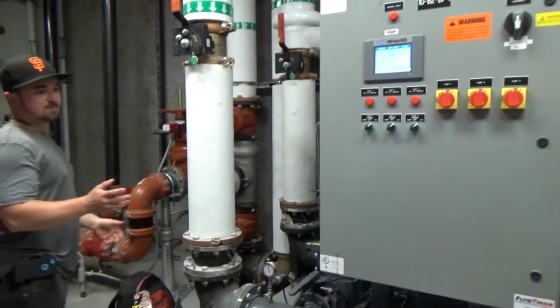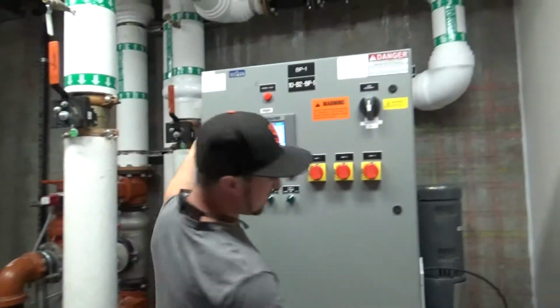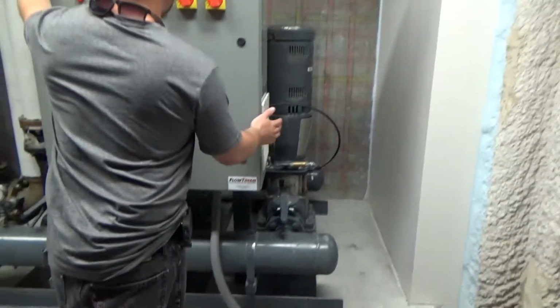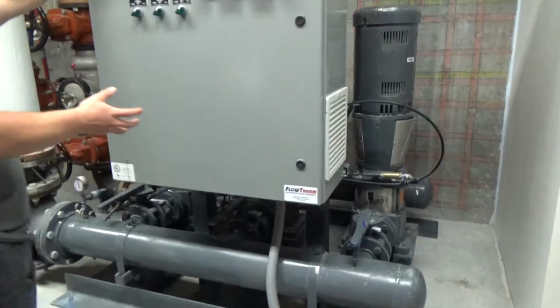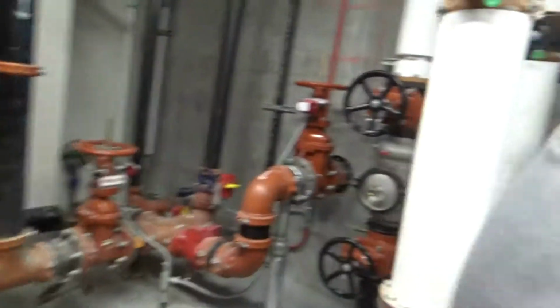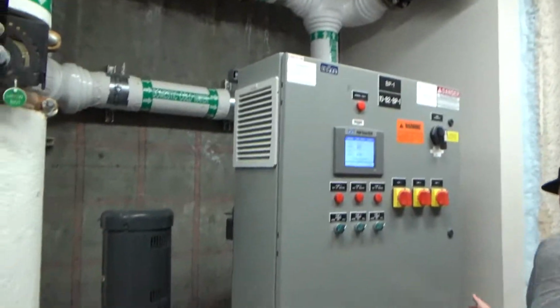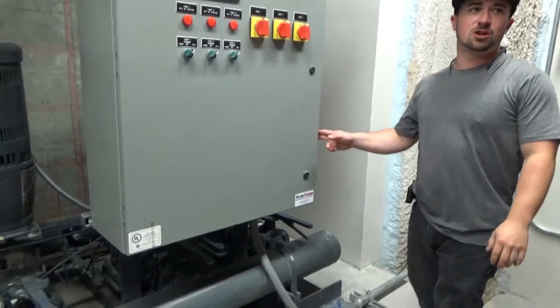So that's pretty much it for the panel. We do have an intake and an outtake, or an exhaust, to pretty much cool down the panel. The fans kick on at 90 degrees inside of here. So this would be your intake. The intake does have a filter on there.